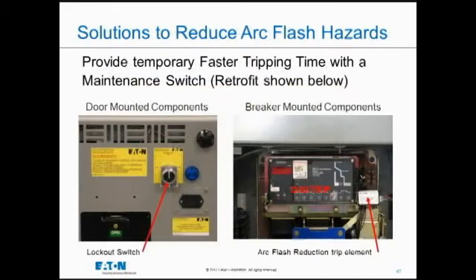This one is on display here at the show, arc flash reduction through a maintenance switch. And maintenance switch has now made its way into the best practice guide as a technique. That's the CSA Z462. The technology is pretty simple. It's more or less, why are we waiting for the circuit breaker to delay tripping if we're working on that particular section of the power system?